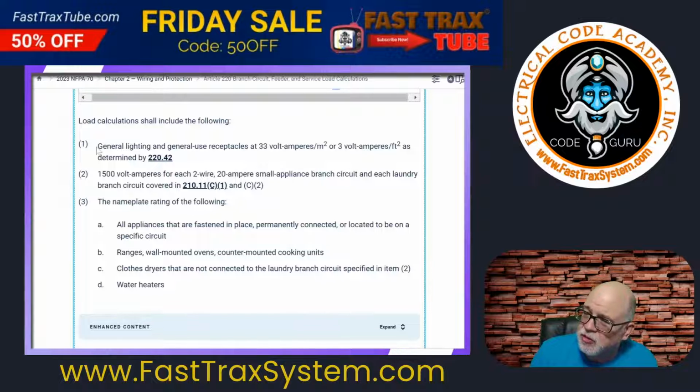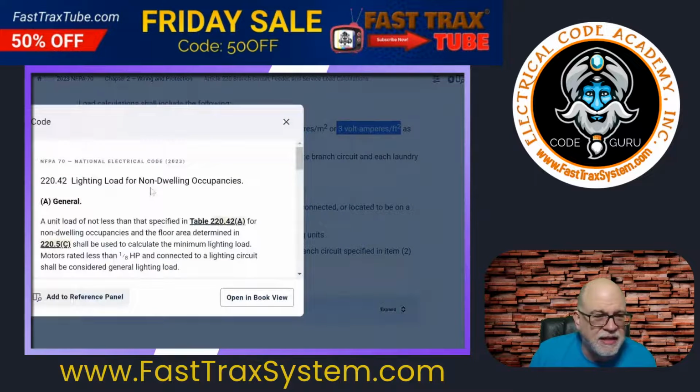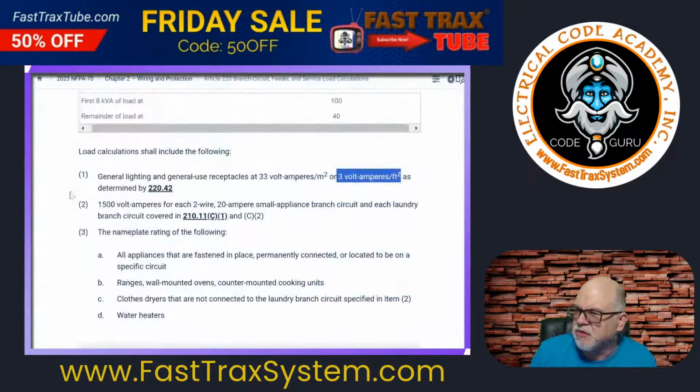First thing you got to do is you calculate the general lighting and general use receptacles at 3 VA per square foot as determined in 220.42. I'll click that so you can kind of see, and a little bit of it will pop on the screen. Again, this is where it talks about lighting for non-dwelling loads, and so on, but not really significant for us here.